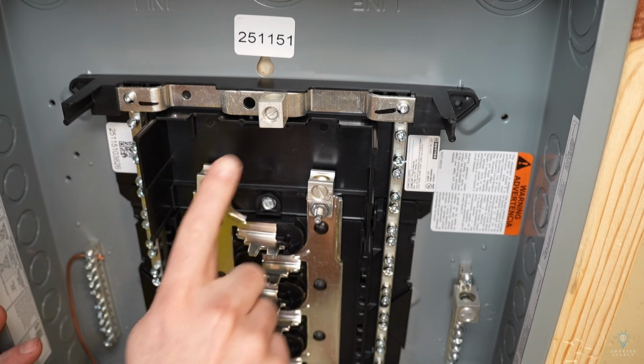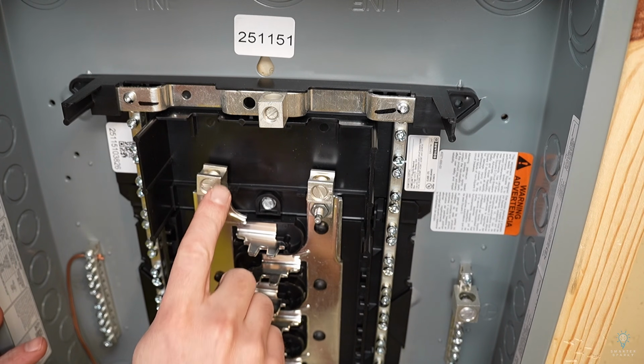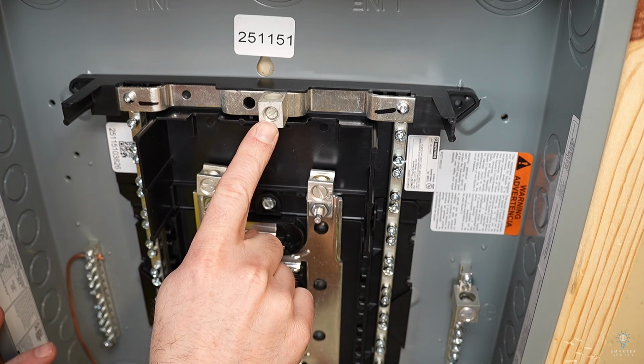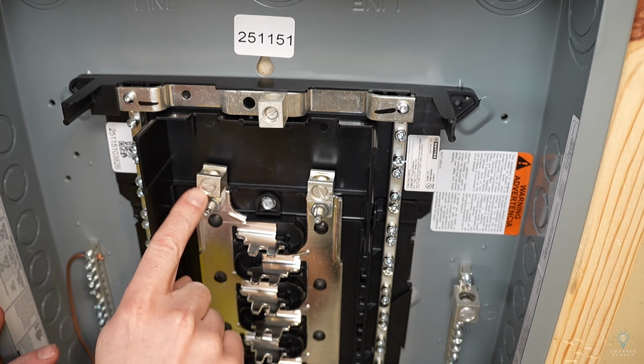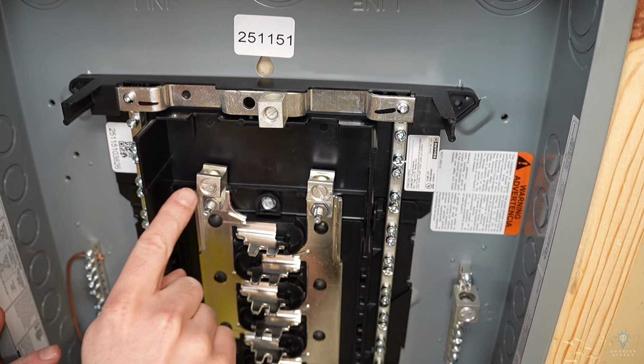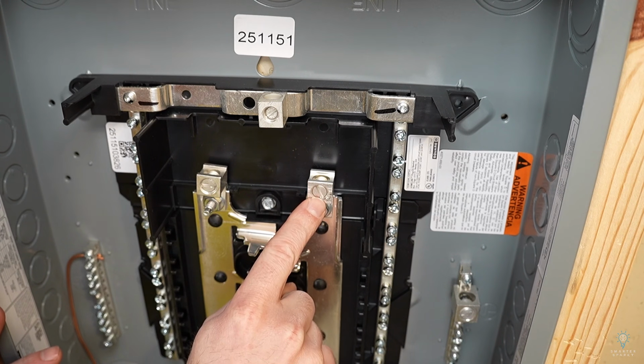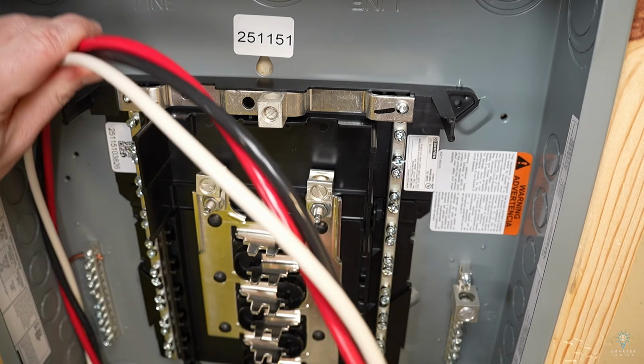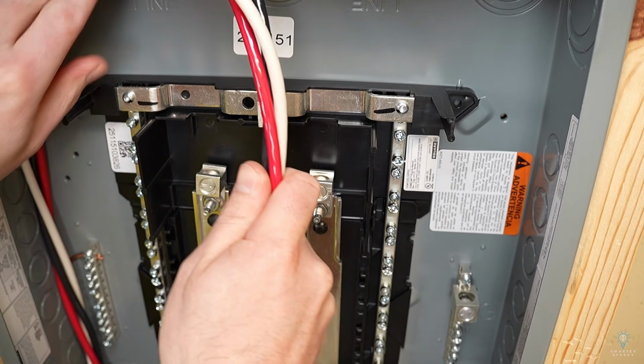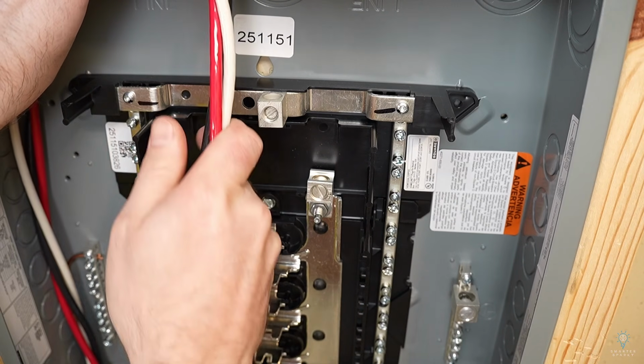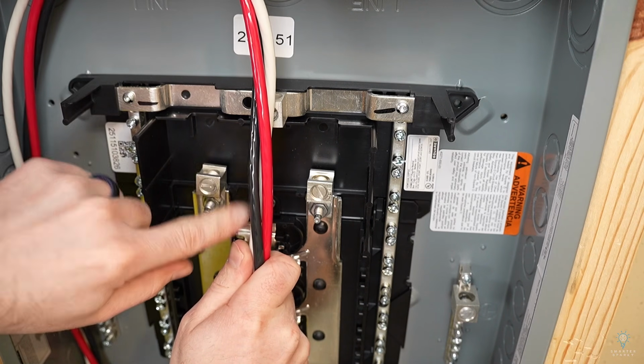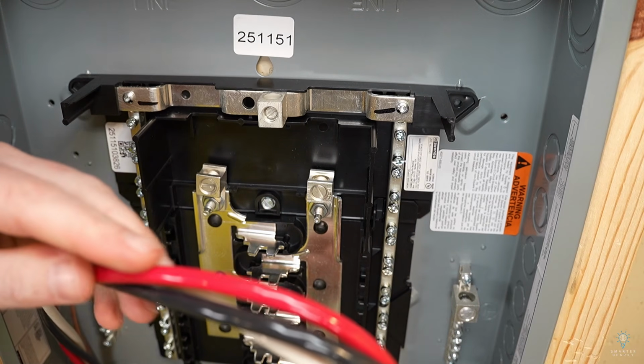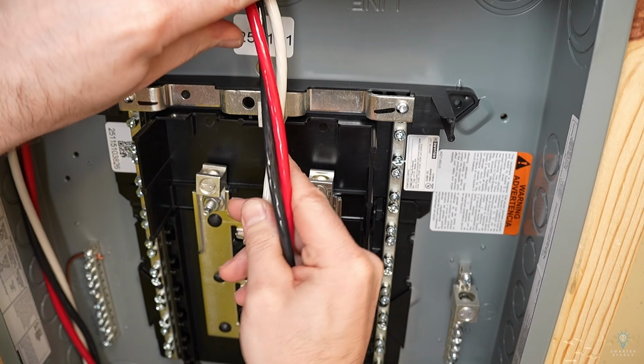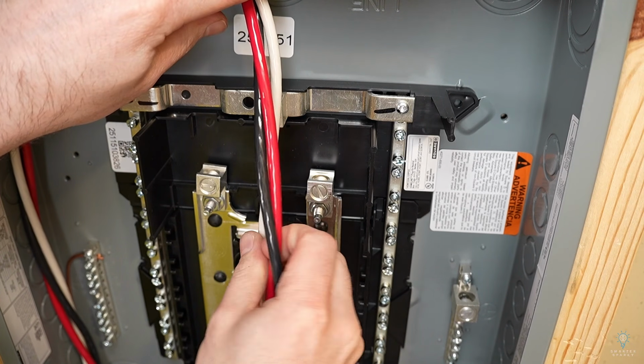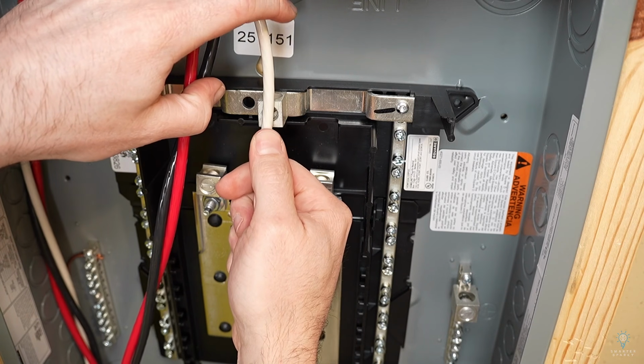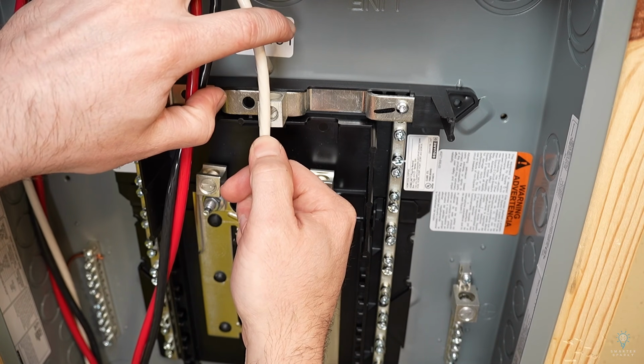Here's a little better view of how these lugs up top here work. Our neutral, again, is going to go to this lug. This is going to be line 1, and this is going to be line 2. So this will be our black wire. This will be our red wire. So I'm just going to fold these wires up into the corner of the panel and bend them roughly into shape so they start coming down the center here. And I'm actually going to keep them wrapped up until about the top, and then that's where I'm going to split them off. So it looks like our neutral will be approximately that long.